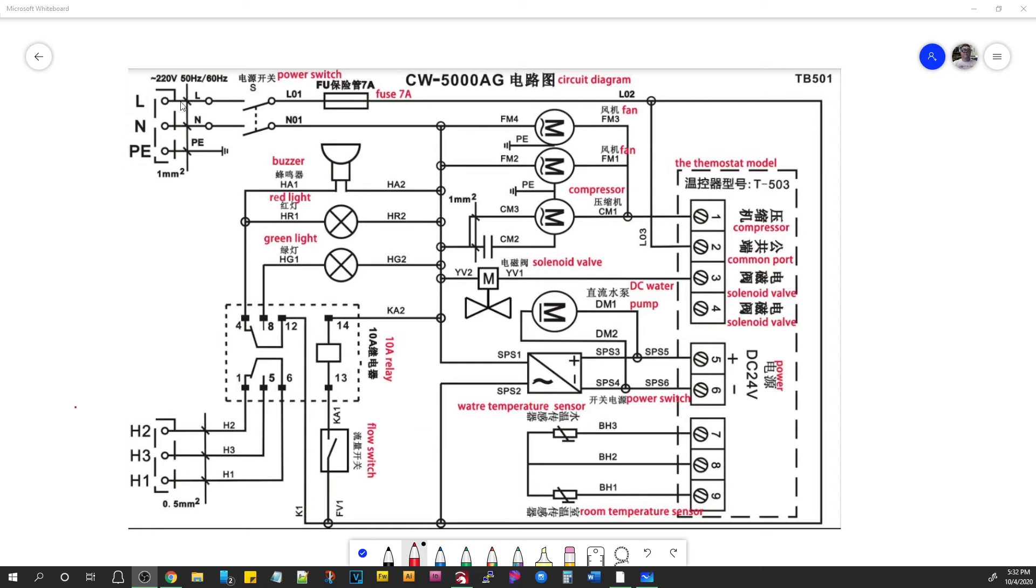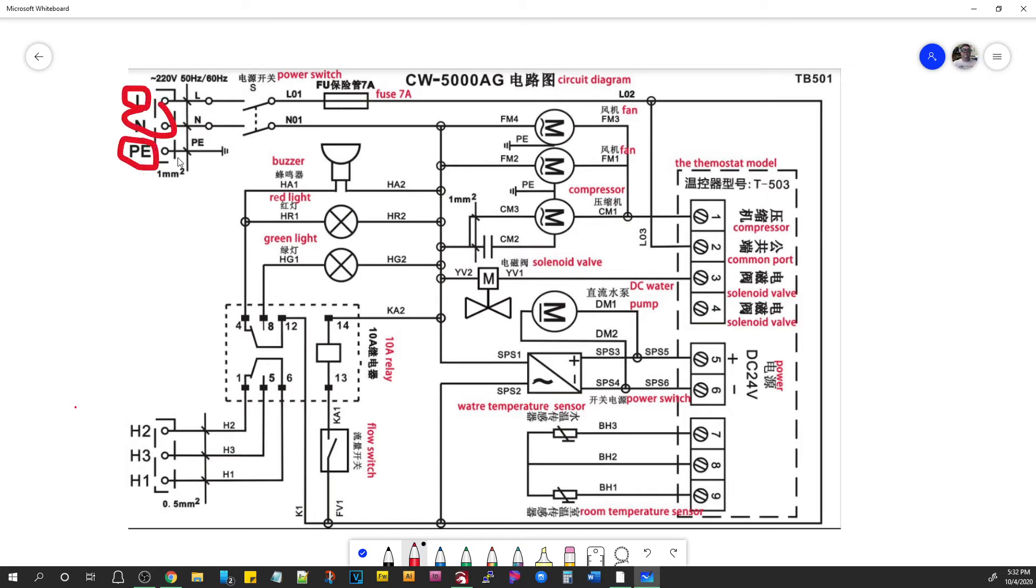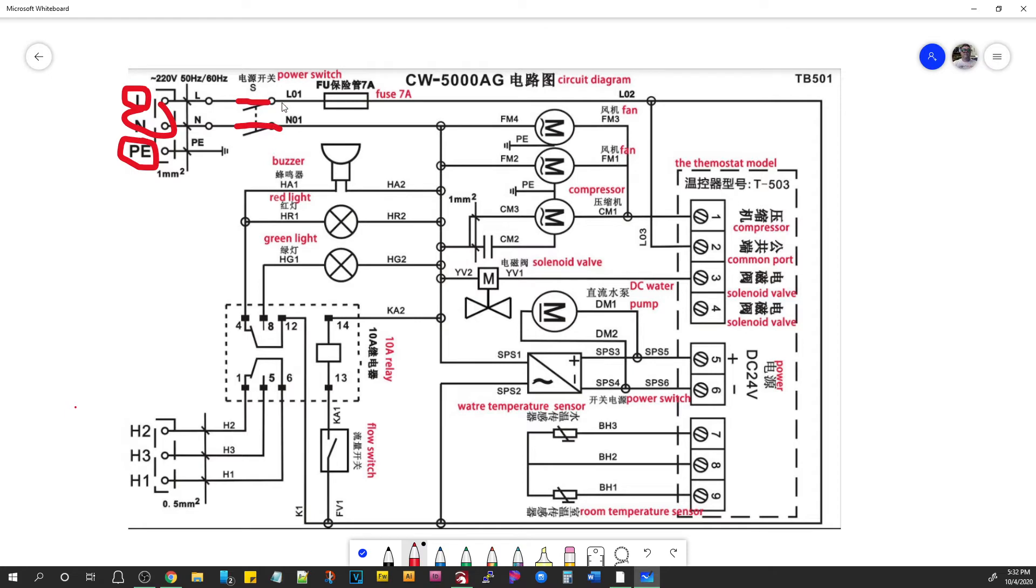Now, this is a Chinese document so it says 220. Of course, we're going to be dealing with 110 at 60 hertz and this is where the power connection goes in, the input for the power supply. There's line, neutral and protective earth or ground. And if you'll notice, this is a double pole, single throw switch. So when you flip it on, it connects the line and the neutral. It completes both of those circuits.